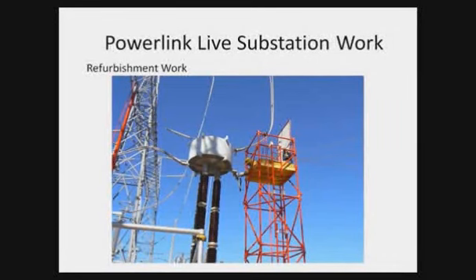Here's a job where we've been pulling line traps out of place. So as we install fibre optic communication networks on our system, the old power line carriers and line traps become redundant. So instead of turning the feeder off to pull them out, we've bypassed these line traps and pulled them out. You need to be very careful, however, working with line traps because there's a voltage difference across the line trap. It can be quite spectacular.